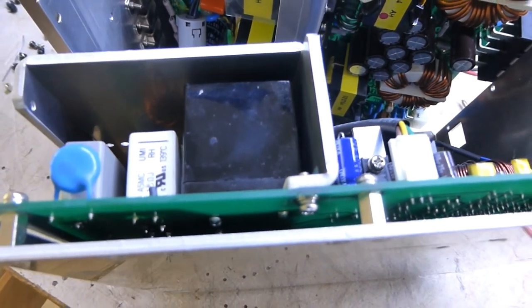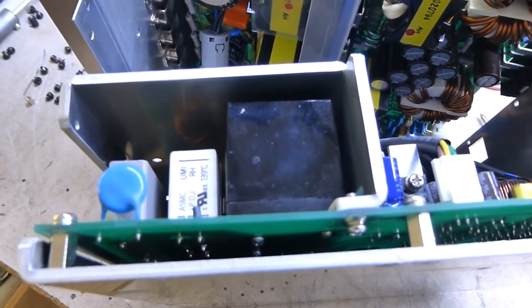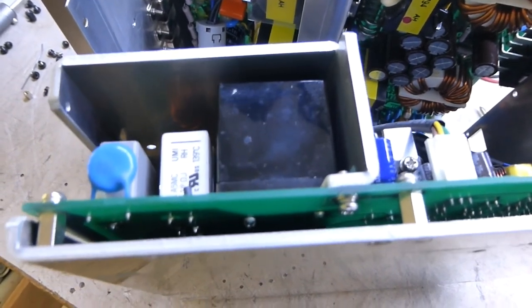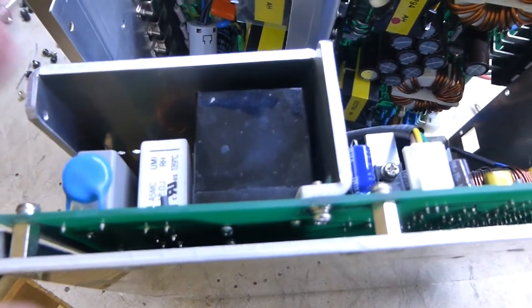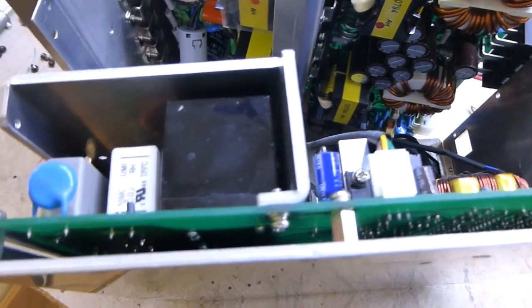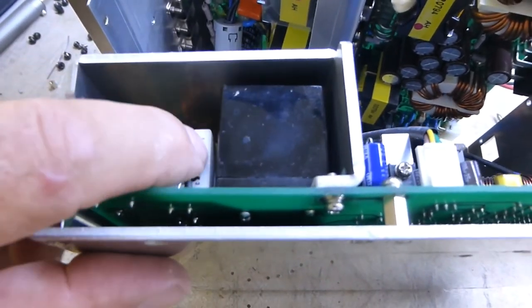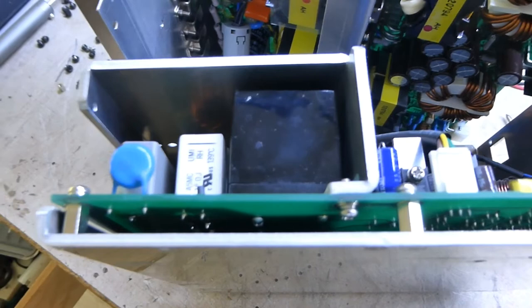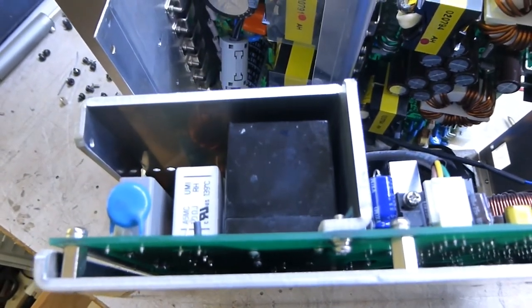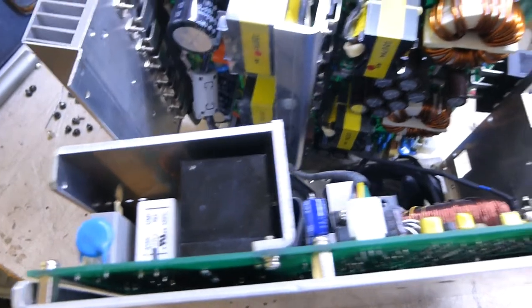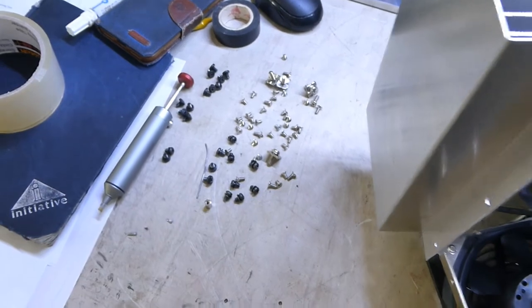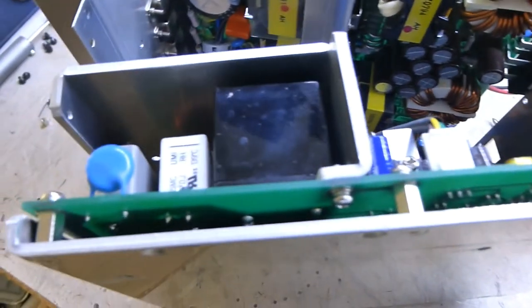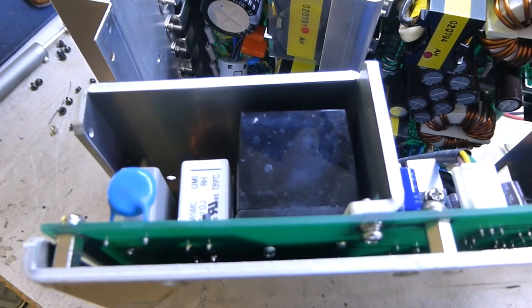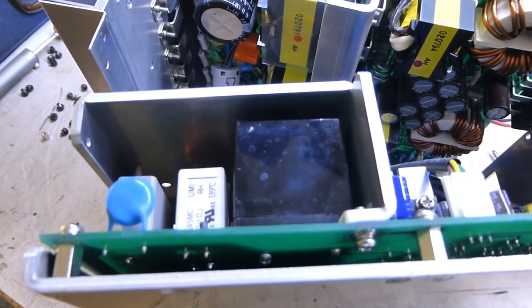And being on an island here, our mains power supply is not great, and you do get brownouts and flickers, and I believe that's the root cause of it. The owner has run this on a UPS since these resistors went the last time, so it's survived probably 2 years, but maybe the UPS is getting a bit jiggered now, who knows. So we're on the route to putting it back together. There's all the screws. I did mention there's a lot of screws to take out, and then we'll be able to test it and get it back to the user.